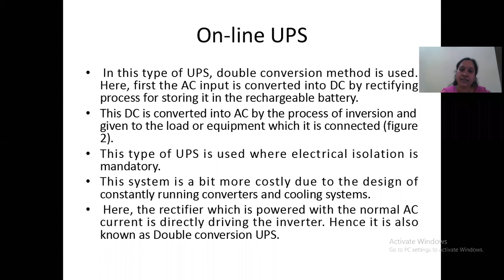This type of UPS is used where electrical isolation is mandatory. The system is a bit costlier due to the design of constantly running converters and cooling systems. Here, the rectifier, which is powered with the normal AC current, is directly driving the inverter. I'll show you the figure. This is how the online UPS works.